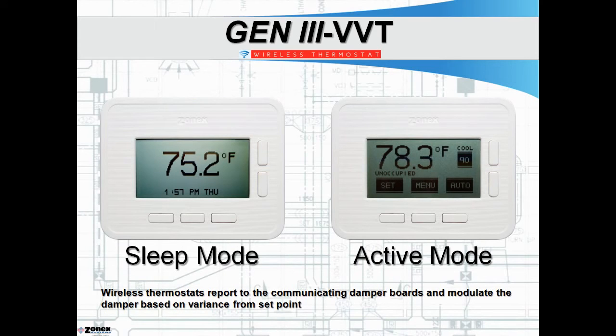The GenIII wireless thermostat is powered with 2 AA batteries. The display is designed to operate in various modes to prolong and extend battery life. The sleep mode on the left is a default display for the system, providing room temperature, date, and time. The active mode is displayed after pushing any button on the thermostat, providing access to set points, menu items, and other features. Regardless of mode, each thermostat works behind the scenes and communicates with its respective communicating damper board, controlling and modulating its damper based on variance from set point.